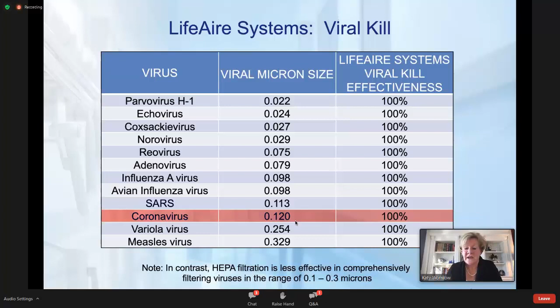On the viral side, we provide a 100% kill of some of the more common and infectious viruses. And as you see, a number of these are quite small. Your HEPA filter is optimal at capturing viral particulates greater than 0.3 microns. It will capture some down to 0.1, but it's not at 100%. So your influenza virus is 0.098 microns in aero diameter. SARS is 0.113, the current SARS-CoV-2 is 0.12. So again, a high likelihood of penetrating HEPA filtration.